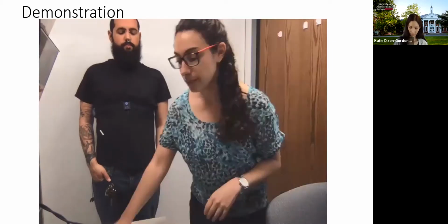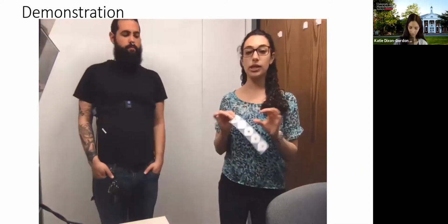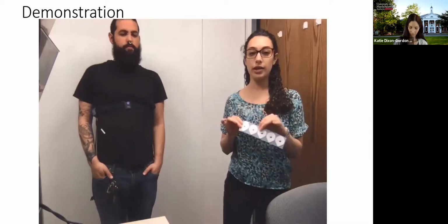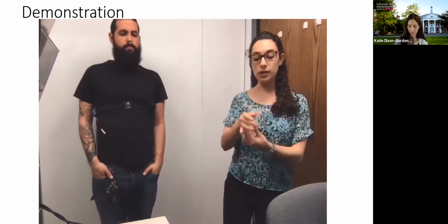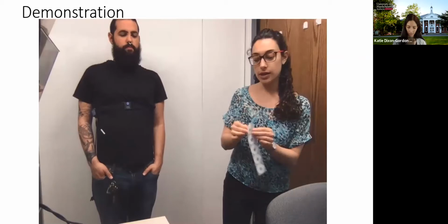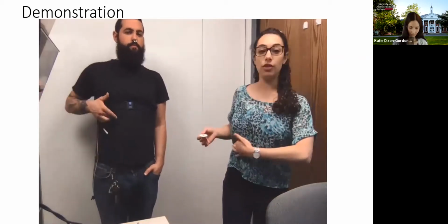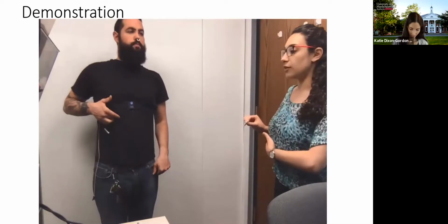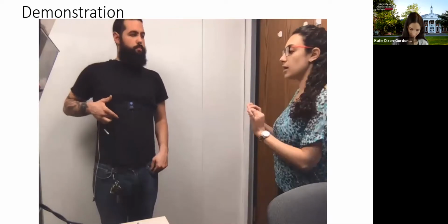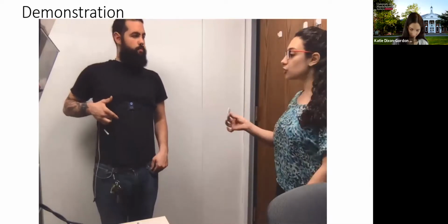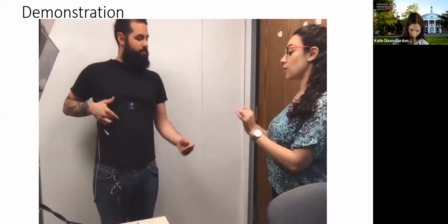So next we're going to go ahead and start placing the electrodes. So specifically we'll need 3 of the ECG electrodes placed throughout the torso. The first one is going to go directly on the right bottom part of the rib. So I'll ask you to identify that bony part of the rib, and then I'm going to give you this electrode, and you're welcome to step off screen and place the electrode directly on the bone or as close as possible.